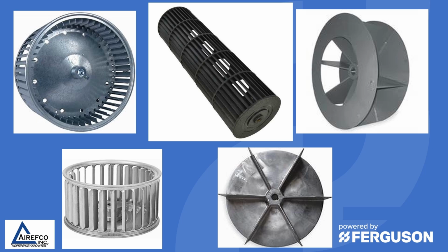As we've said many times before, homeowners notoriously tell you that they have changed the filter when they really don't. And when the filter gets plugged and maybe some of the dust gets past the filter and gets into the blower wheel, it can cause inefficient airflow delivery because the blower wheel is dirty. So make that a part of your routine maintenance to check the blower wheel to make sure that it's clean, it's centered properly in the blower housing, and it's delivering the correct amount of CFM for that particular unit.